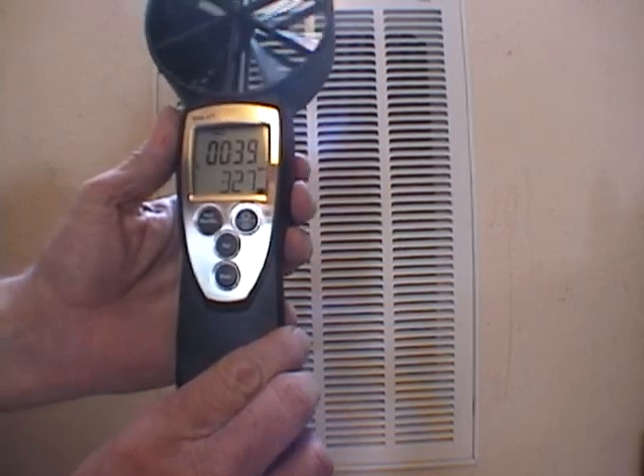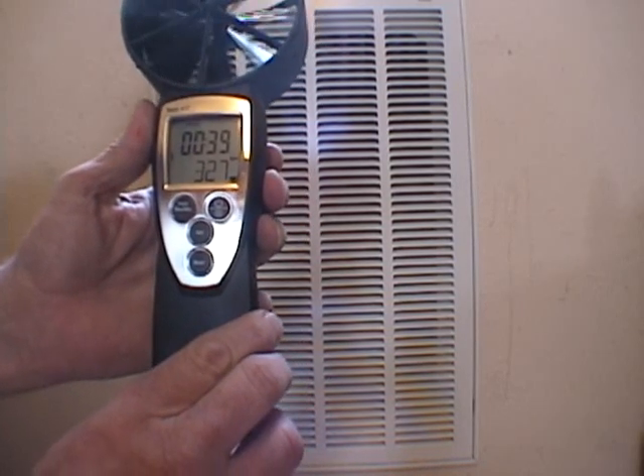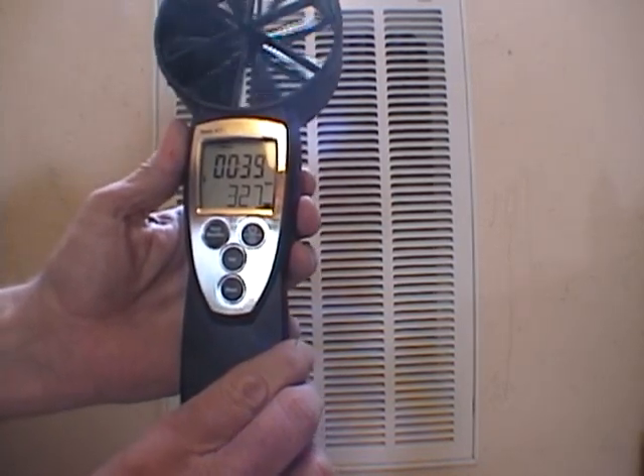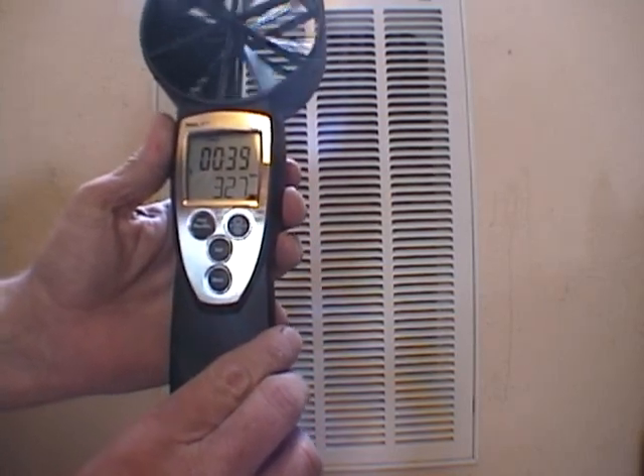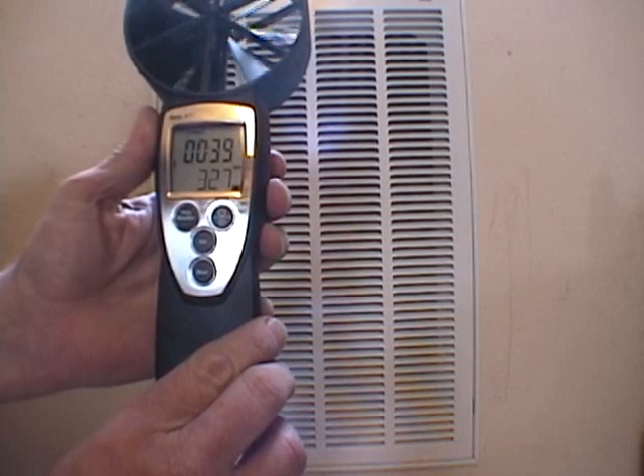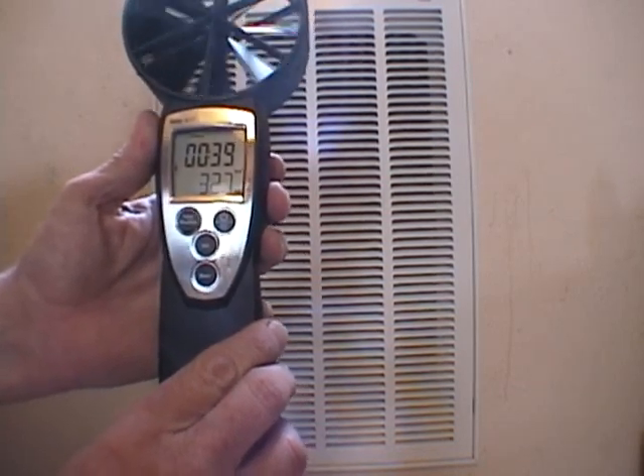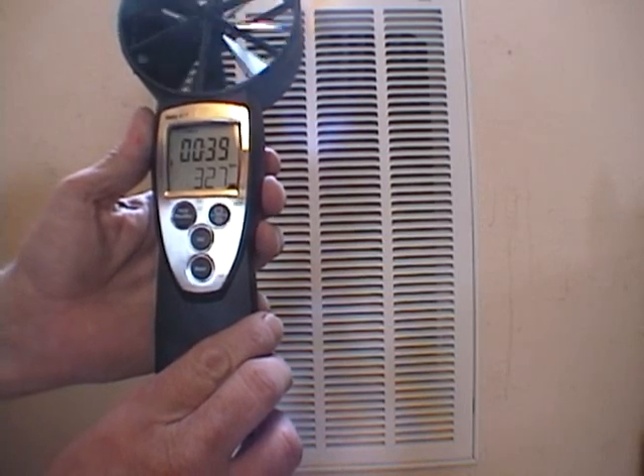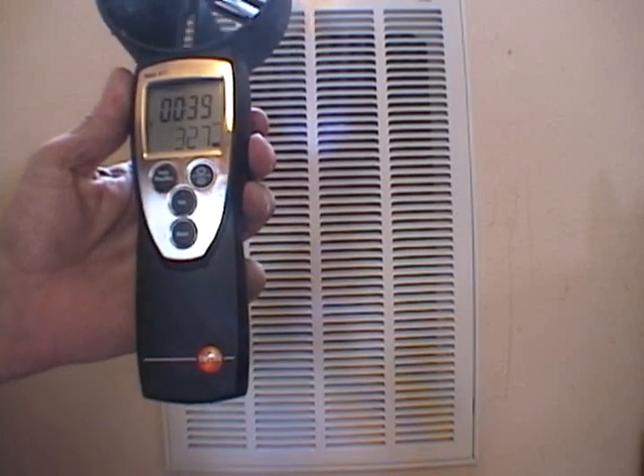Typical design is you don't want anything over 400 feet per minute for a return grill. So now we can measure this grill, use the square inches and square feet, and calculate our CFM system or input it into our spreadsheet or software and let it calculate the CFM. Let's measure this grill now.